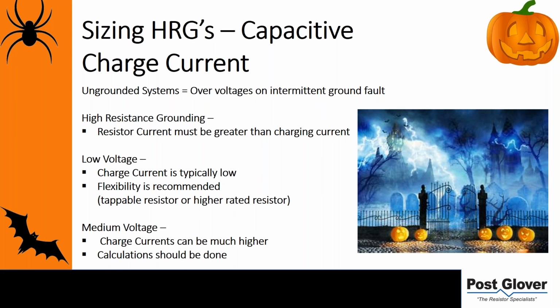Now, what happens if you're in a feed and you don't have the information? I would say budget yourself accordingly so you could have the option for later. But a lot of times, if you can feasibly estimate the amount of wire lengths and sizes, you could probably do it. Wire length in general accounts for about 80% typical of your typical capacitive charging current. So if you know what your wire is, you have a large understanding of what that may be.